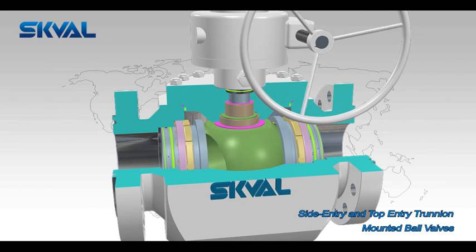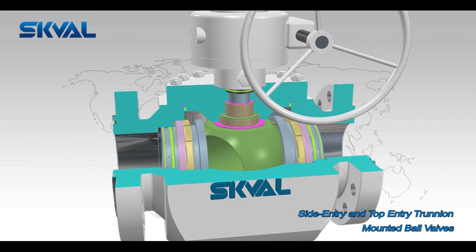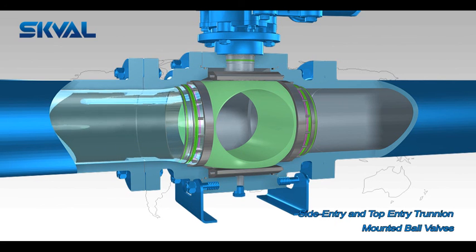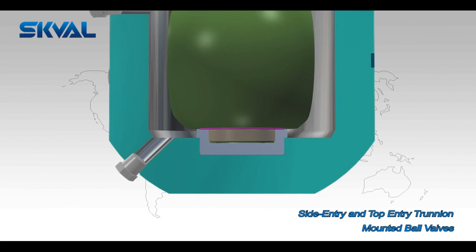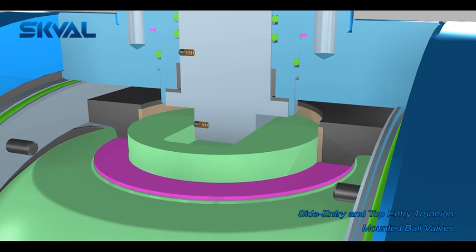The ball is mounted on trunnions or supported by plates with low friction bearings, reducing torque so the user saves on the cost of actuation. Pressure drives the upstream seat into the ball while the ball remains stationary. This double block and bleed design per API 6D means upstream and downstream seats isolate the cavity.